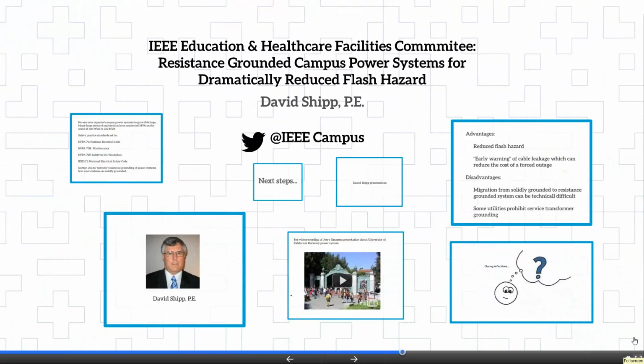and you measure line to ground voltage and you think I'm going to get 277 volts, for example, but I got 480 because there's a ground fault on it with some little high voltages, you need to know how to deal with a safety issue on the voltage piece. And about 2 hours of training for maintenance crews, as we've retrofitted these in other industries, will meet the requirement of the code for the safety piece for the maintenance personnel. And other than that, it's done. Now, that's the concept that I've been doing, and I've been literally trying to take what I've learned in the other process industries and put it in different ones where it makes sense.